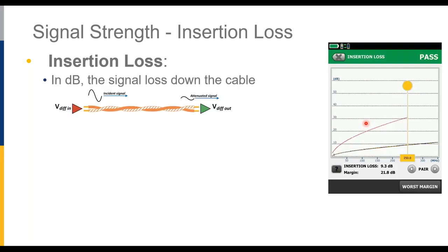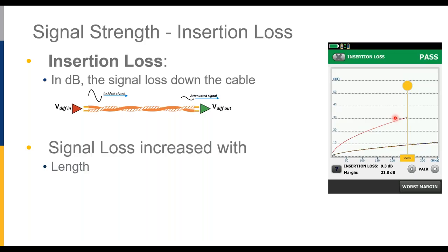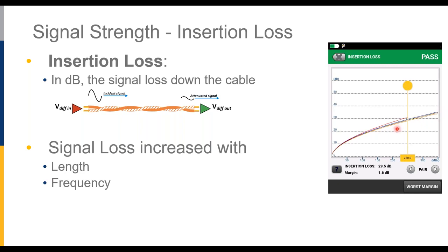After continuity, we look at signal strength — measuring how much insertion loss there is. We inject a signal into the cable and measure the attenuated or reduced signal on the far end. A graph shows signal strength versus frequency, with a red limit line from the standards representing the maximum acceptable insertion loss. Insertion loss increases with both length and frequency — you'll notice the graph goes up and to the right. At maximum length of 90 meters, measured values get close to the limit line.